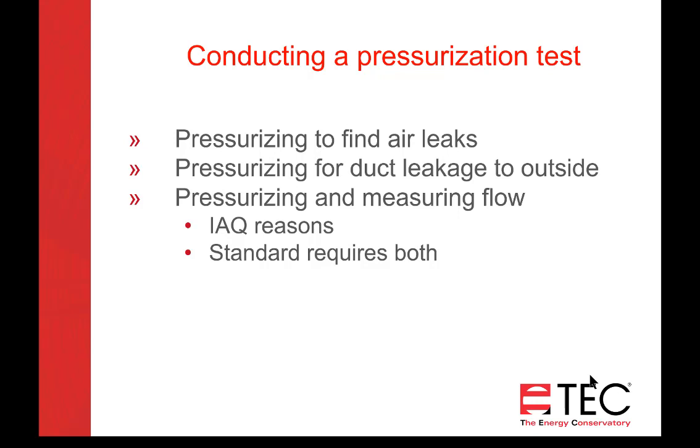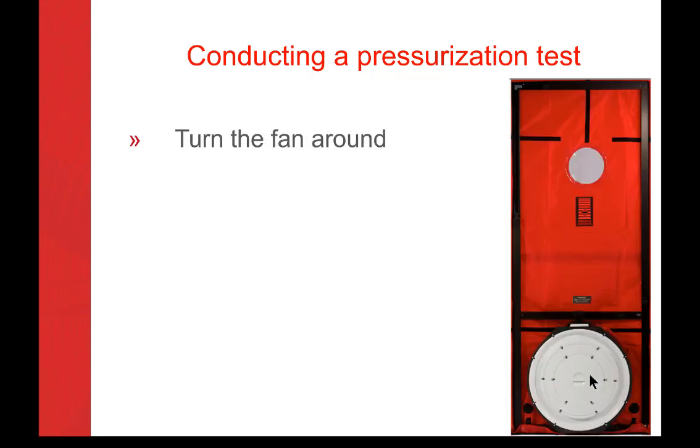And you may be doing that for IAQ reasons. If you go into a house and there's a real strong moldy smell and you suspect it's in the walls, you don't want to be pulling air in through those walls and spreading the mold spores throughout the house. Protocols that you're following for asbestos or vermiculite may require you to pressurize. And some standards require both a depressurization test and a pressurization. So that may be the case too, where you're required to do tests in both directions.